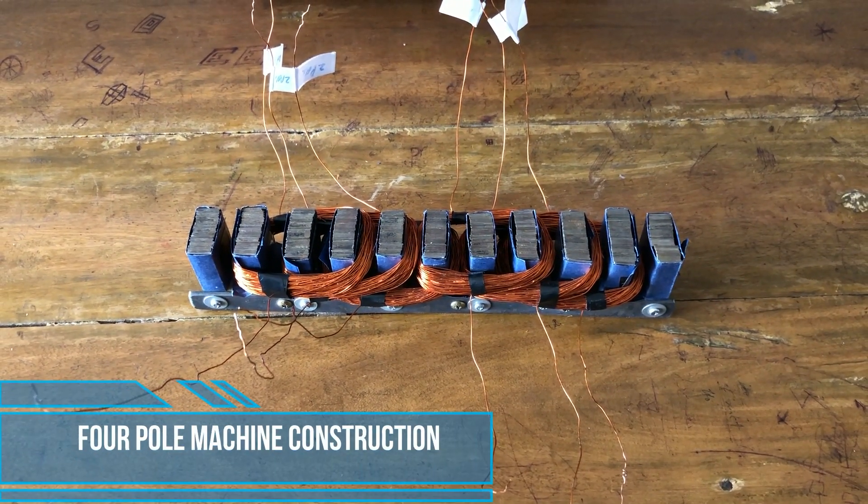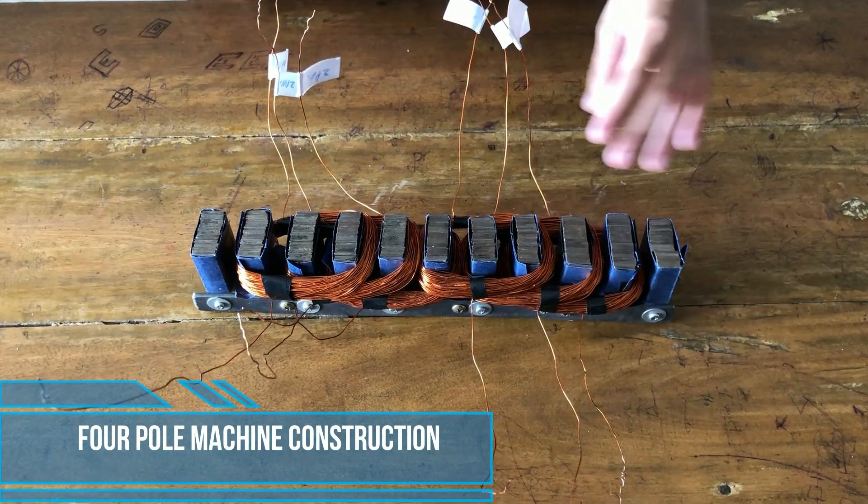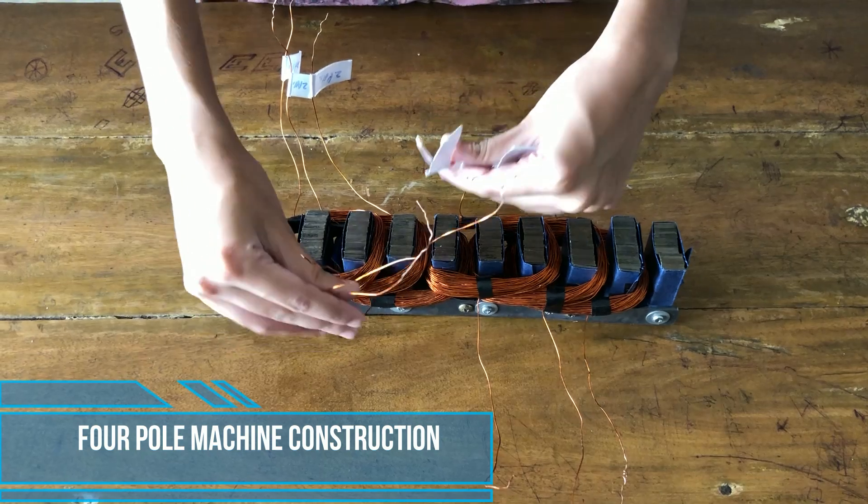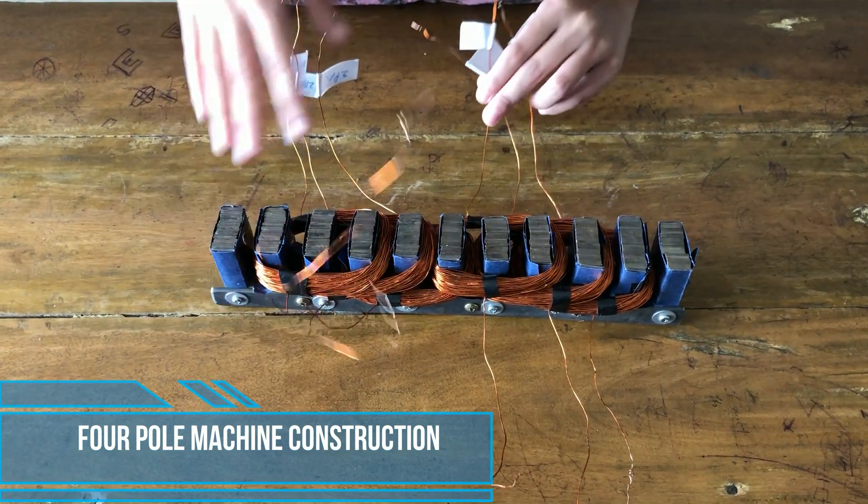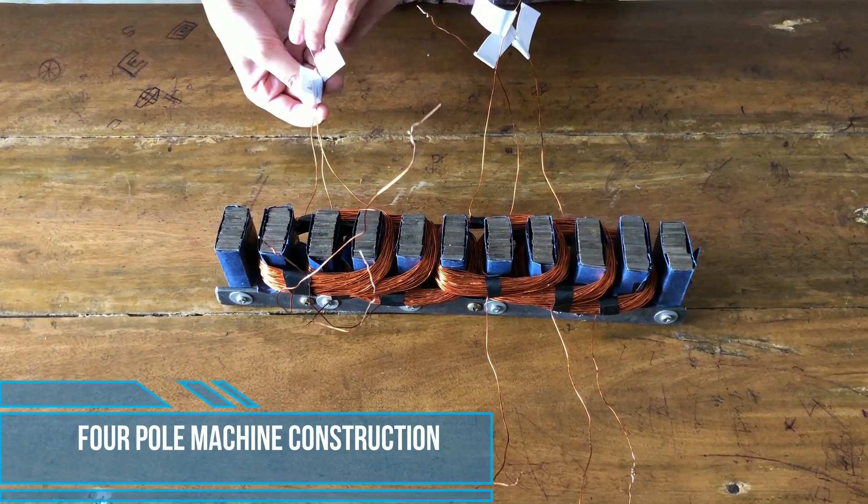Now, we shall proceed to the four-pole configuration. The input terminal will be as it was in two-pole. However, the output terminal will be connected with this terminal of coil 2 instead of this one, and this terminal will be shorted together and will act as a neutral point here.